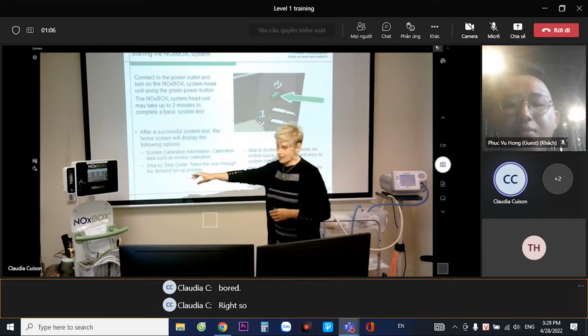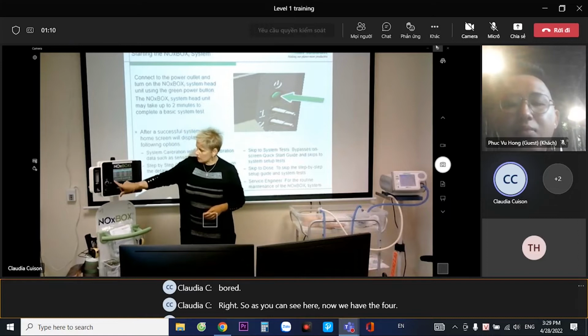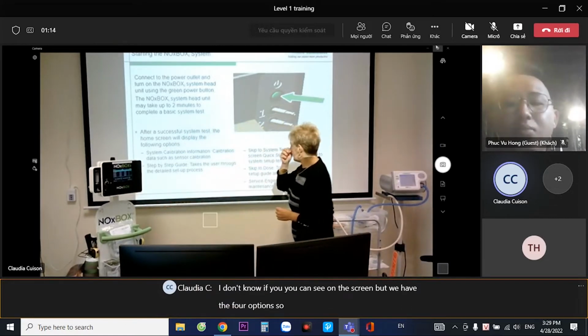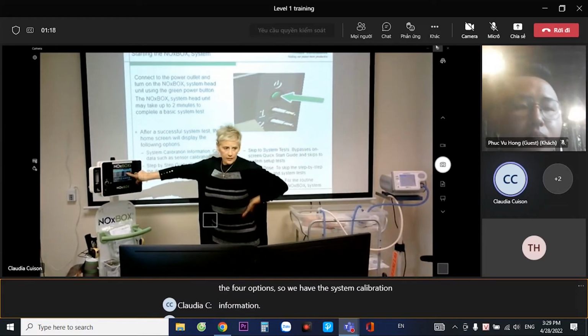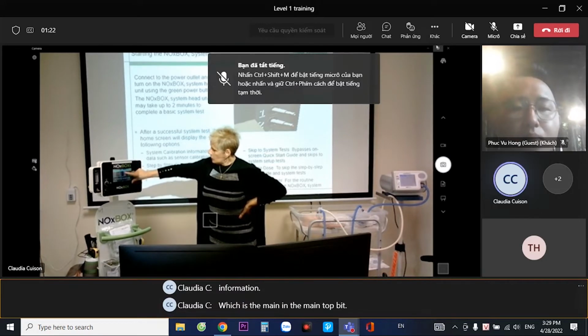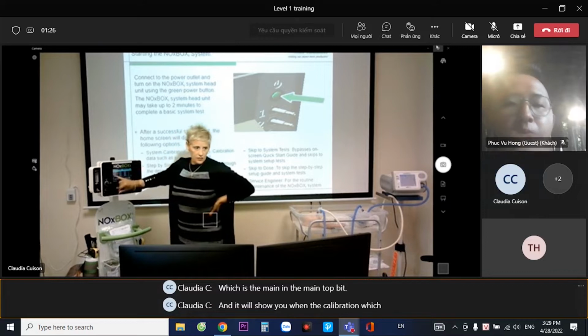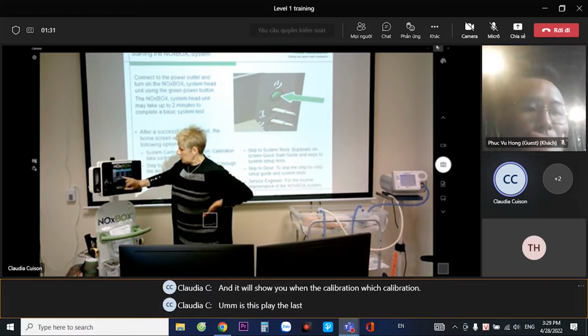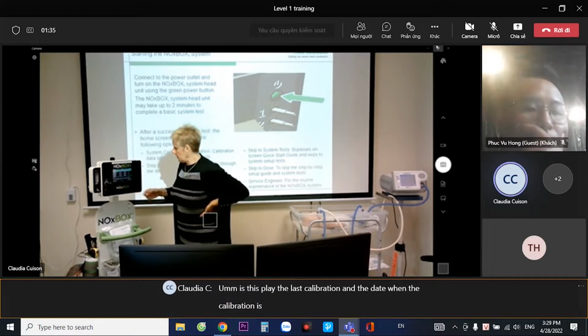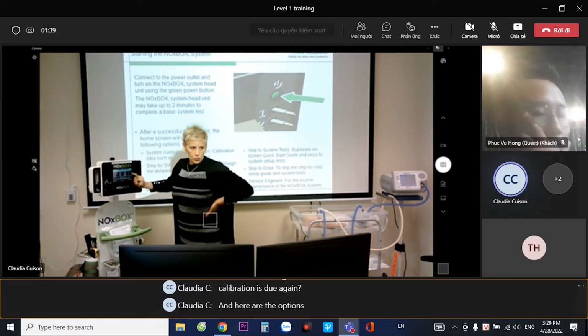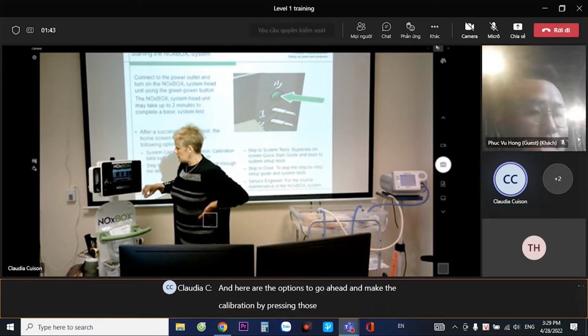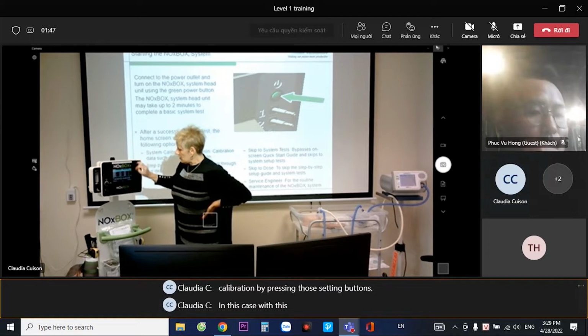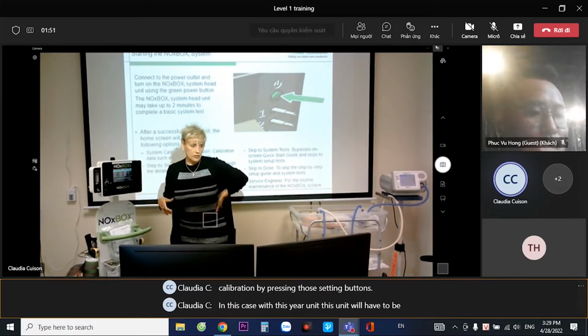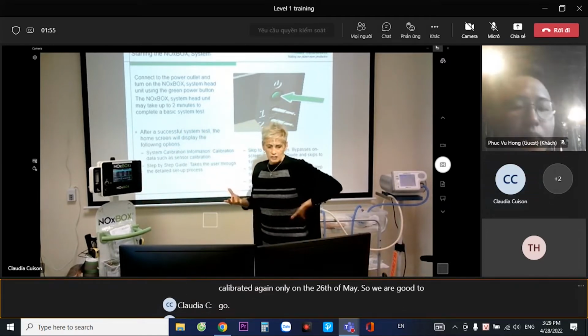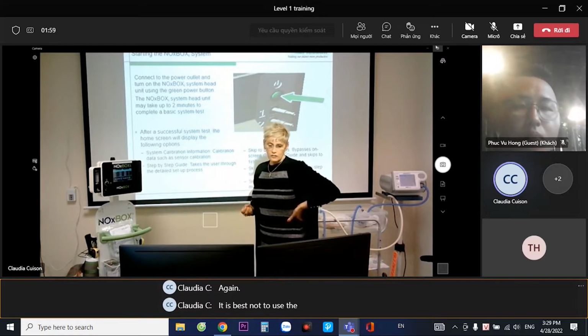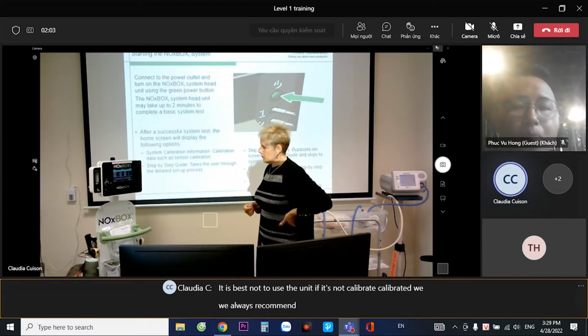Right. So as you can see here now, we have four options. I don't know if you can see on the screen. We have the system calibration information, which is in the main top bit, and it will show you which calibration was the last, and the date when the calibration is due again. And here are the options to go ahead and make the calibration by pressing those setting buttons. In this case, this unit will have to be calibrated again only on the 26th of May, so we are good to go. Again, it is best not to use the unit if it's not calibrated. We always recommend calibration before using.